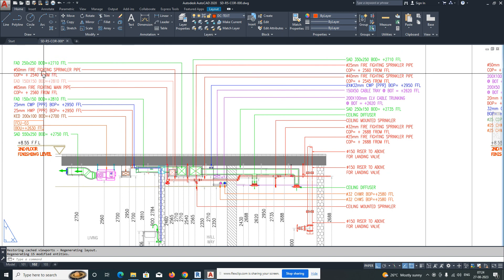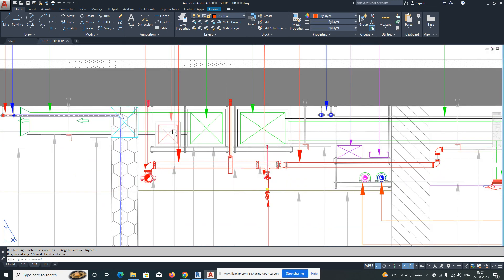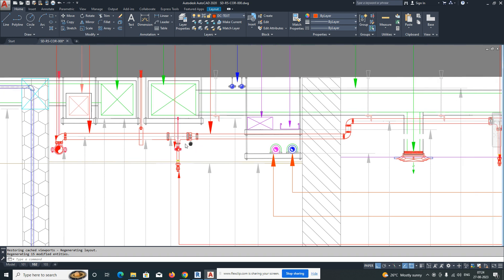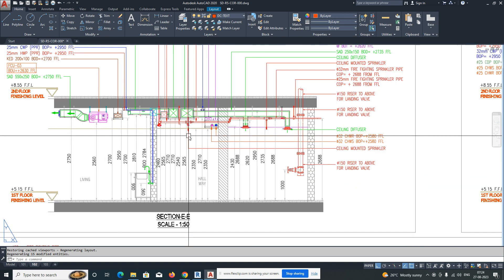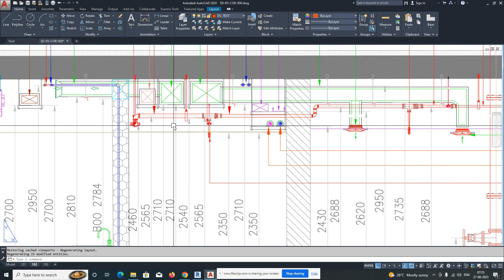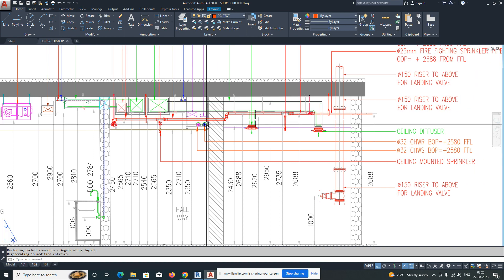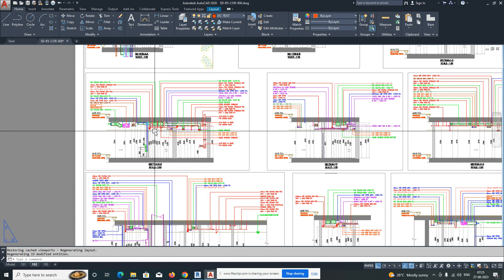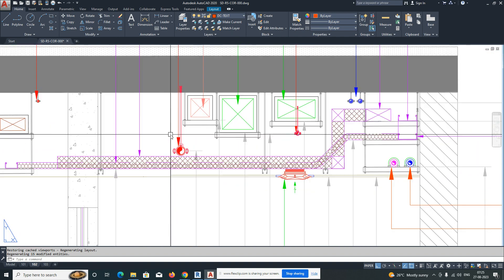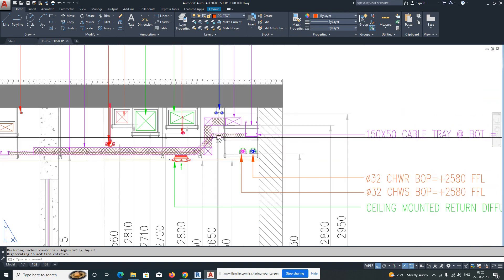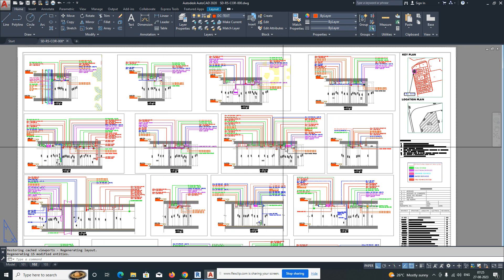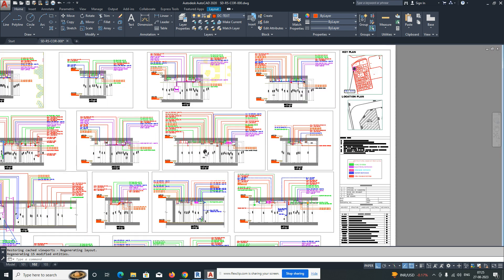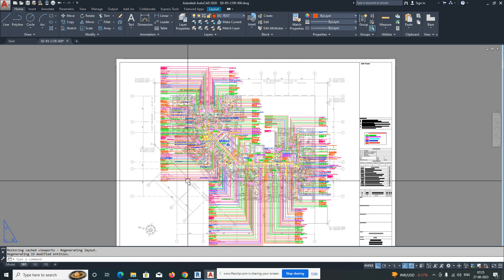For example, this is a section where the ducts are going one way, fire fighting below, and sprinklers above — all need to be shown in the coordination model. We create shop drawings with specific levels. Once you prepare the shop drawing, we need to coordinate all the services — for example, cable tray going one way and ducts going another — without any clashes. I will show you how to do this in AutoCAD.